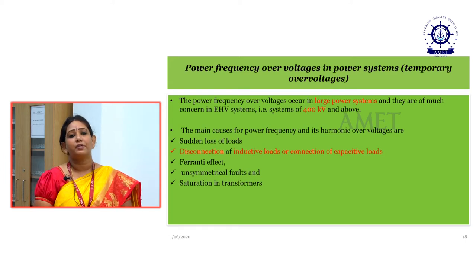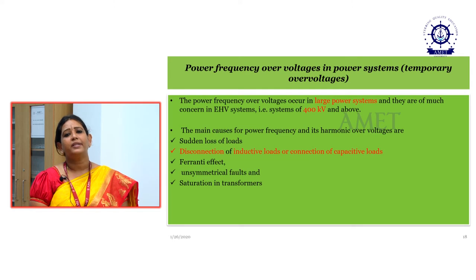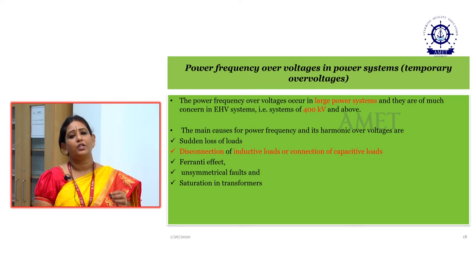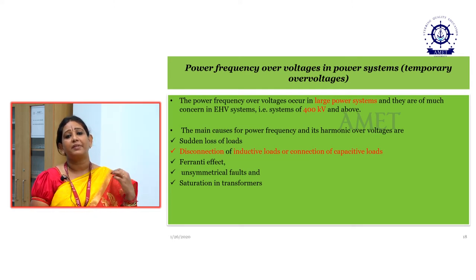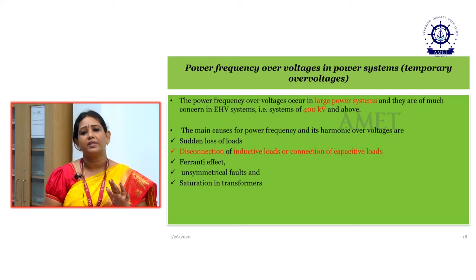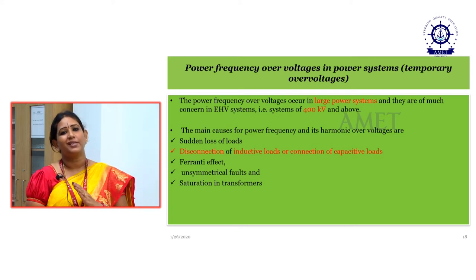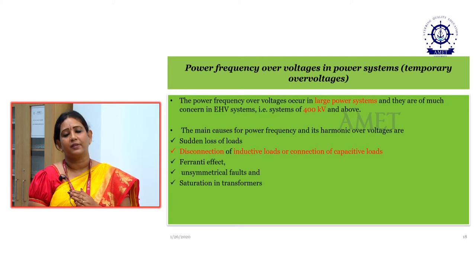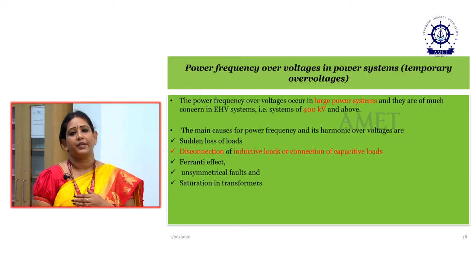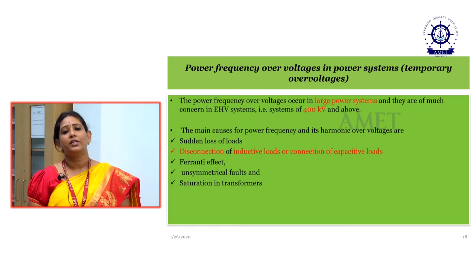It's called power frequency over voltage, otherwise called temporary over voltage. Why is it named temporary over voltage or power frequency? Because these really happen at only one frequency, say 50 hertz to 60 hertz, on the utility services. Utility means on the distribution side. The previous cases were all on the transmission network, and these types of voltages are experienced in the utility services.